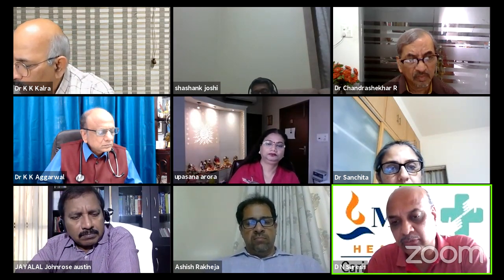Just adding to what Dr. Chandrasekhar said, we actually created a BSL level 2 lab recently during COVID to do RT-PCR testing. The room size was the same, 10 by 10, slightly over, with an anteroom of about 8 by 10. We provided exhaust with a HEPA filter, and air conditioning was a normal split AC. That cost us about 1.5 lakh rupees. The air goes through a UV stage and then through a HEPA filter, with an auto indicator showing whether the UV or HEPA is working. We checked the air quality of the exhaust air with an air culture, and there were no traces of any virus.